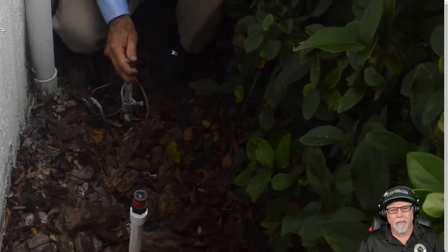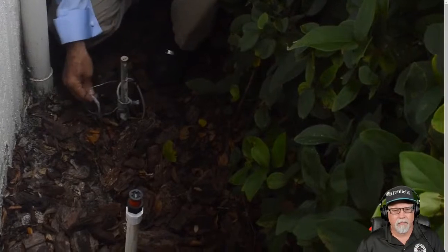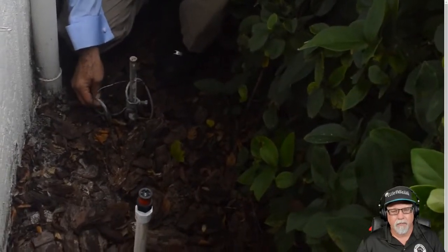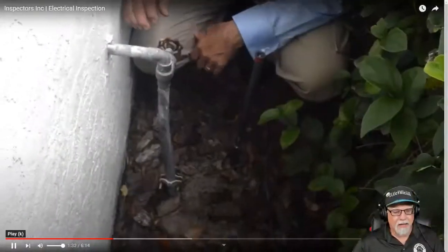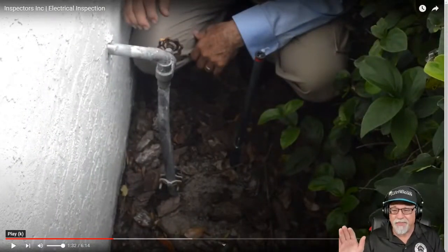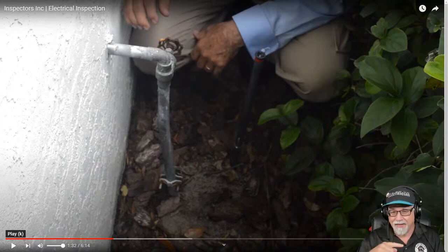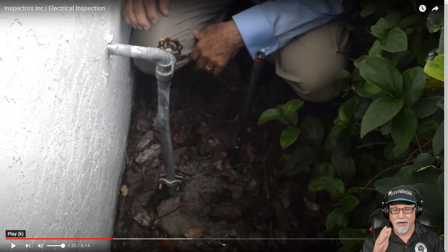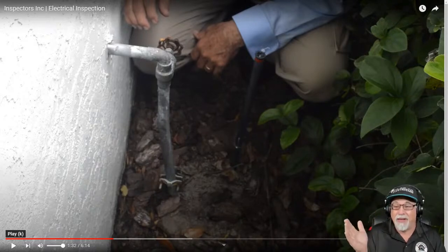The other one we talked about is when the electrical ground is connected to metal piping, assuming the house has metal piping. So let's take a look at that. Again, it has nothing to do with the house having metal piping inside. Nothing to do with that. And I am quite shocked here that there is no water meter here. So it must be a water meter on the inside, whatever. Otherwise, they get free water.